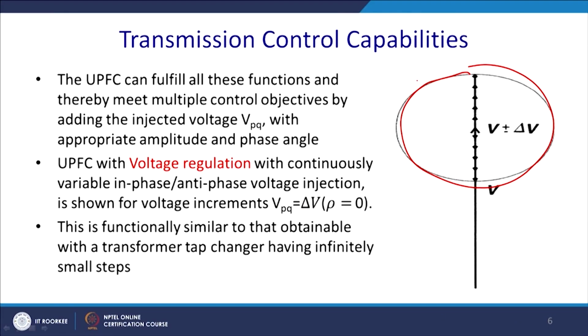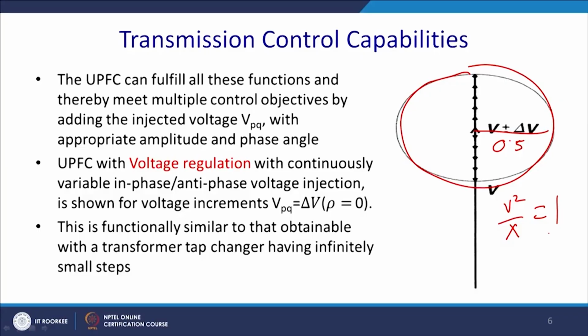We call this circle the sphere of influence, or the circle of influence, and it will have a magnitude of 0.5, where V square by X is considered to be 1 per unit. So, you can compensate anything within this sphere of influence. Let us see how it will compensate voltage sag limited to minus 0.5 and swelling of 0.5. UPFC can fulfill these functions and thereby meet multiple control objectives by adding the injected voltage VPQ with the appropriate amplitude and phase angle. It can inject any phase and any angle within this circle.